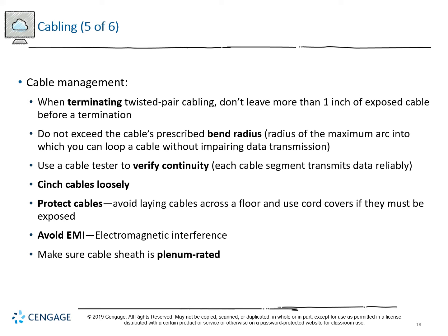Cinch your cables loosely, so if you look back at the rack, you'll see that the cables are looped together, but it's not compressing it down so tightly that you see the jackets getting dented or squeezed into a highly compressed position. It just keeps them kind of grouped. In certain cases, if they can afford it, they'll often use something like Velcro to be able to have a reusable cable management system. Just because it's a lot easier than working with zip ties. You can loosen them a little bit more easily and be able to replace the cable with a lot less stress.